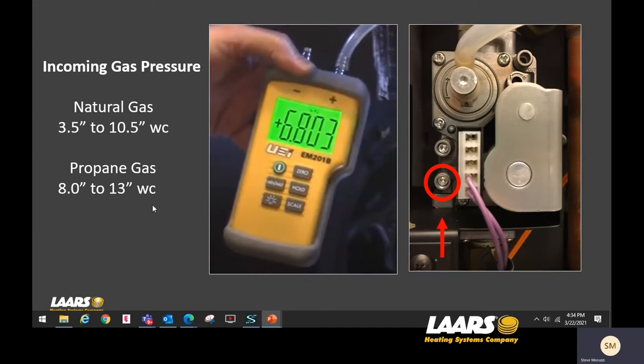This is right on your nameplate. Here we're showing 6.8 inches of water column for natural gas on the incoming barb to your gas valve. Your gas line comes in and that barb closest to the incoming line is where you get your reading. We should never see greater than a one-inch drop on light-off and running of the boiler. Sitting idle — static gas pressure — it's reading 6.8, so when it's running or lighting off, we should not drop below 5.8.